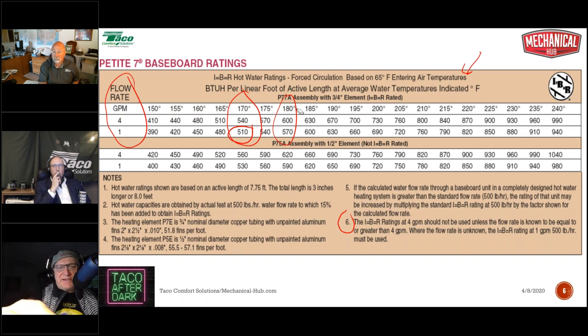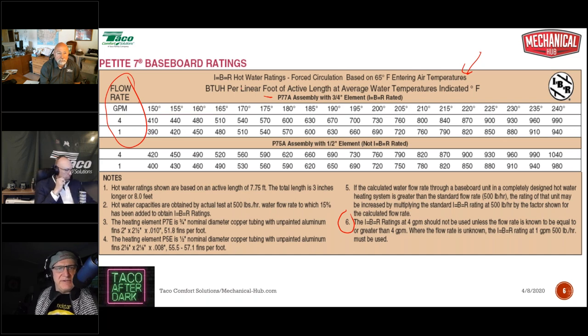Another interesting tidbit that'll be surprising if you take a look at this. The upper chart is for what they call P77A assembly with 3/4 inch element. And the lower chart is for P75A assembly with 1/2 inch element. If you take a look at the two outputs, you will find that the 1/2 inch element, in fact, has greater BTU per foot output than the 3/4 inch element. Well, everything about this says this does not compute. How do you get more output out of a 1/2 inch element baseboard than you do out of a 3/4 inch element baseboard? That doesn't make any sense. Well, again, we have to understand baseboard and we have to look at the notes.